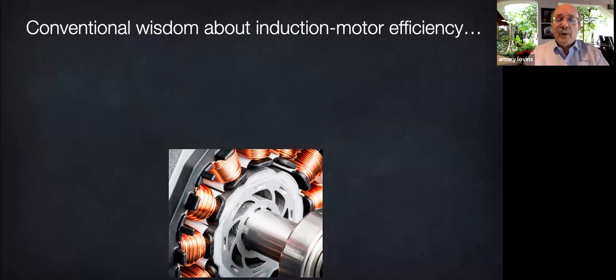Now, those improvements typically save about 15 or 20% of drive system energy and pay back in a few years, but they spread slowly, at most at the rate of routine motor failures, but usually slower because many failed motors are repaired rather than replaced, usually multiple times. 5 or 6 is not unusual.